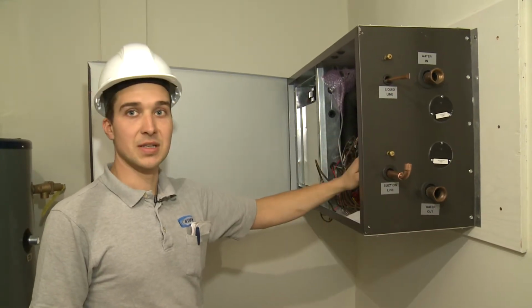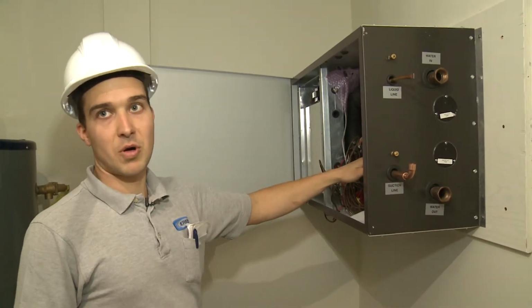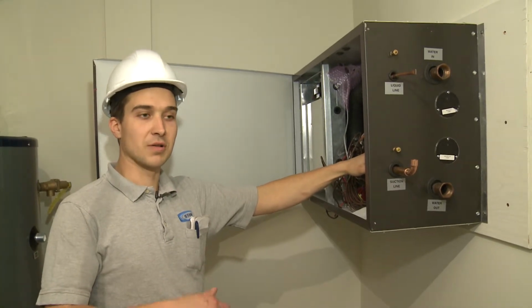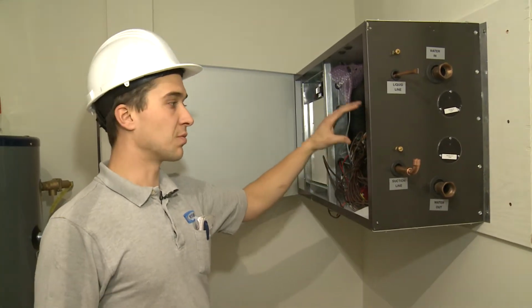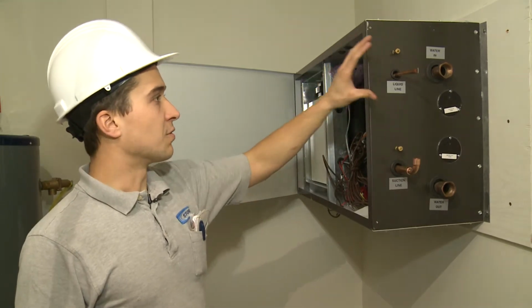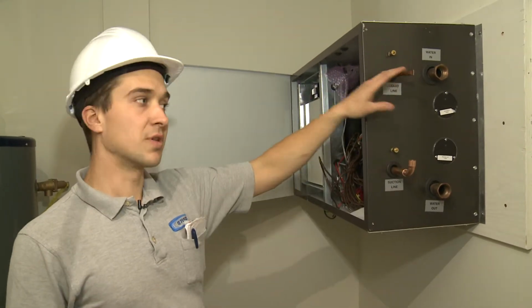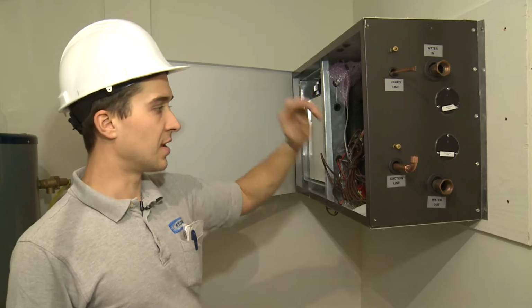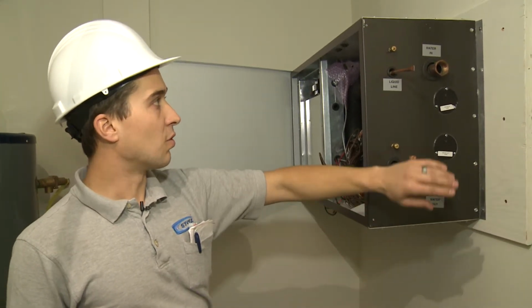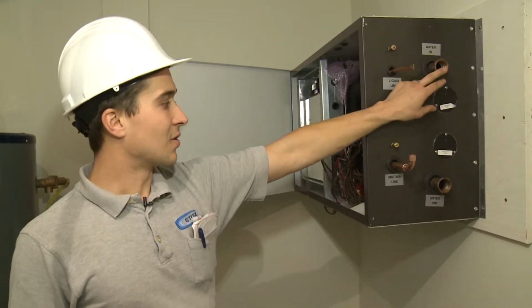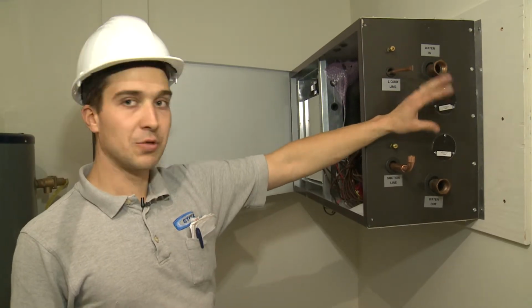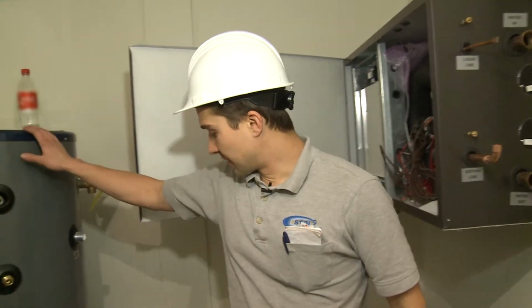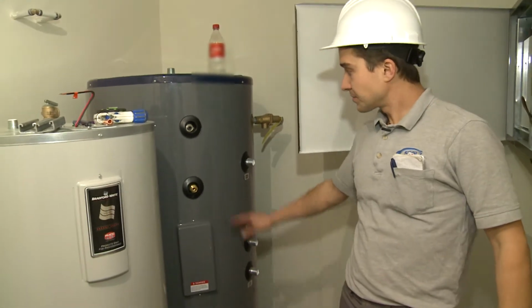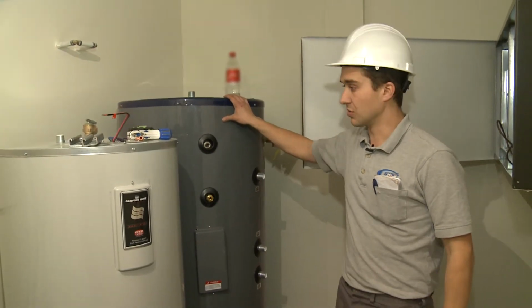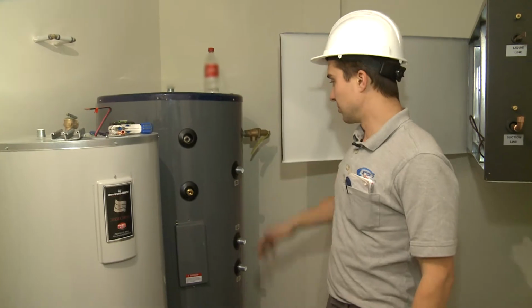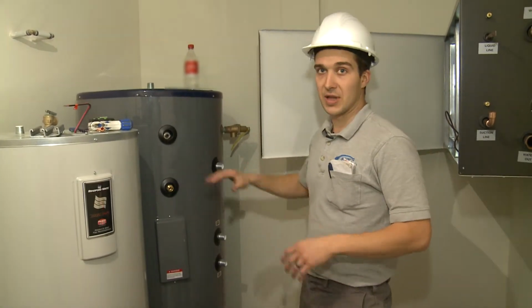So depending on the heating load for the house, how many taps or showers are running, decides how much capacity is needed. So like a traditional hot water tank is always 100% capacity, regardless of the load or how many taps are being used. This one will modulate accordingly. So the refrigerant lines here, similar to the air handler, they go outside to an outdoor unit, and then the cold water in, cold water out, in and out, go here, and it'll be pumped or piped to this holding tank that has a heat exchanger in it for all your domestic hot water. So it's a combination of an on-demand system, and you still have storage tanks.